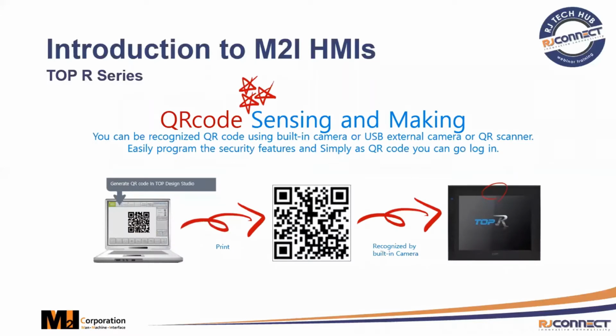The QR code sensing adds the ability to identify, let's say, an operator that has specific rights on the PLC, on the HMI. So let's say, for example, a manager comes, he scans his QR code, you would be able to set points and do a lot more than an operator typically would be able to do. So an operator would only be able to start or stop the machine, etc., where a manager can actually change parameters, for example.